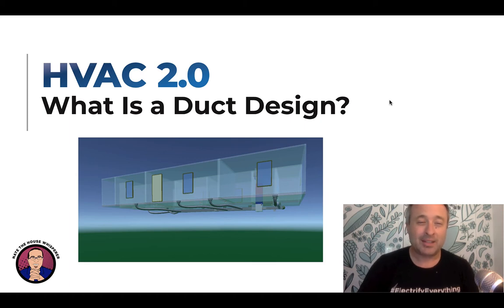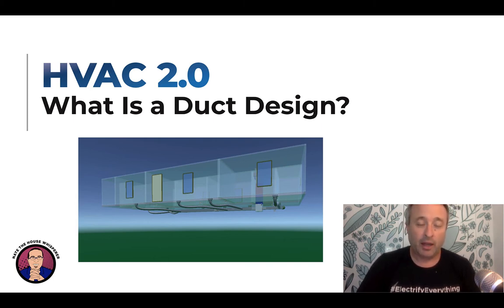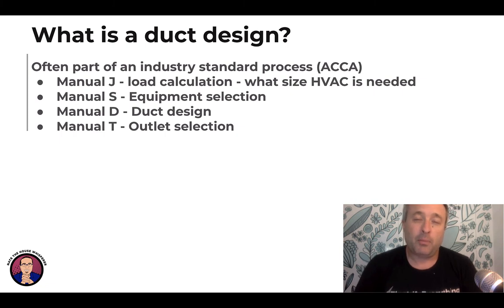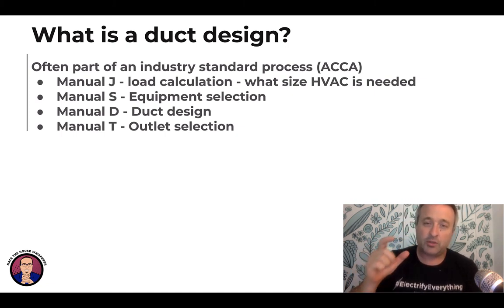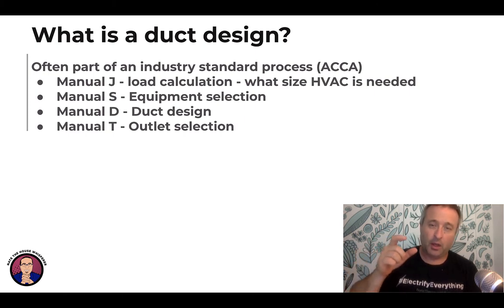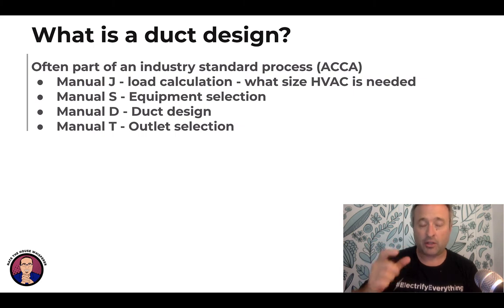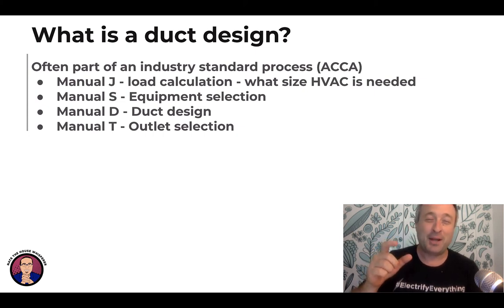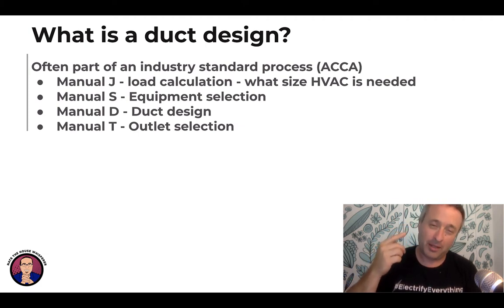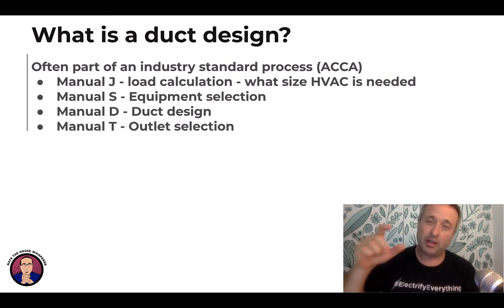So let's go over what a duct design is. This is actually a duct design for my house — it's about to get a heat pump, and I wanted to get a design for it so I can do that this winter. A duct design is a piece of the industry-standard HVAC design process from ACCA — the Air Conditioning Contractors of America. There's a four-step process. First, you do what's called a Manual J — that is the load calculation, figuring out how much it takes to heat or cool your house on that very hot or very cold day.